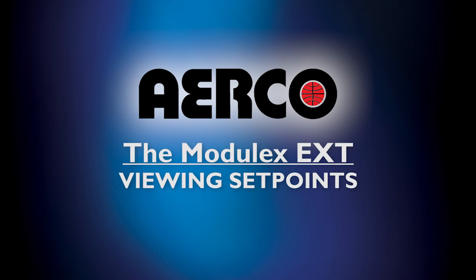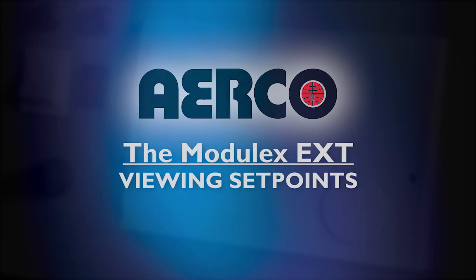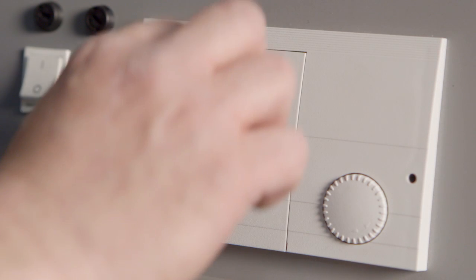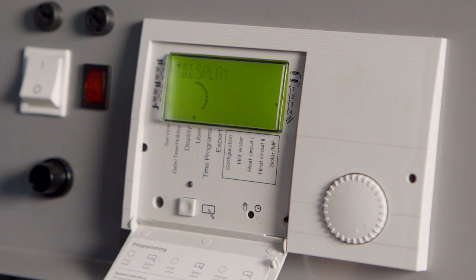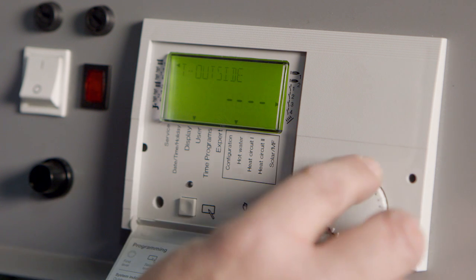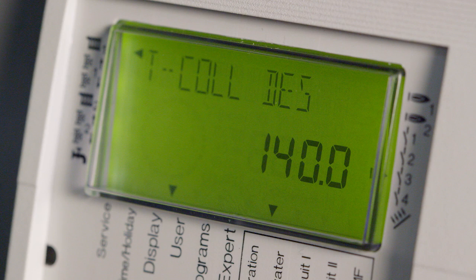Here's some additional information on how to view set points. Let's begin by showing you how to view the set point in the constant set point mode or indoor-outdoor reset mode. Open the E8 panel door to get to the display menu. The first submenu item displayed will be installation. Press the program key to enter this submenu. Then, turn the rotary knob clockwise until this is displayed along with a corresponding temperature reading. This reading equals your boiler set point in degrees Fahrenheit.